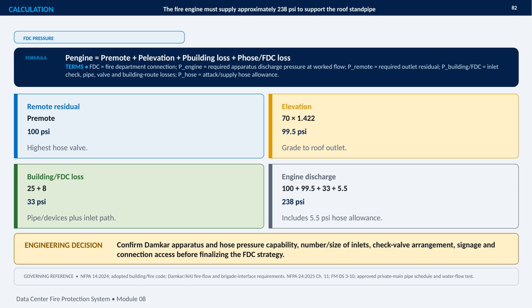This is an engineering decision, not just a theoretical result. Before finalizing the FDC strategy, I need to confirm the Damkar apparatus and hose pressure capability, the number and size of inlets, check valve arrangement, signage, and connection access.